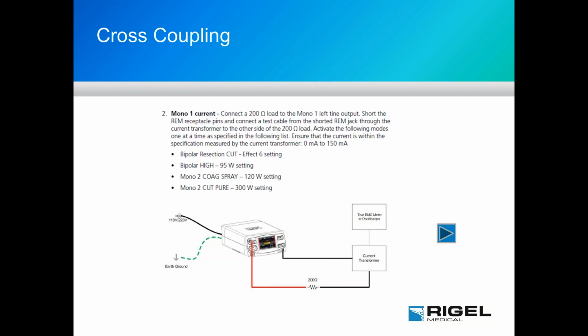And the manual will have us go through, as will our test procedure, looking at output monopolar 2, looking at bipolar, looking at ligature while we energize monopolar 1. And then going over energizing monopolar 2 and looking at all the different outputs to be sure there is no current, no power being directed to that output port. I'm not going to stress you out by showing all those, but we do have one example.